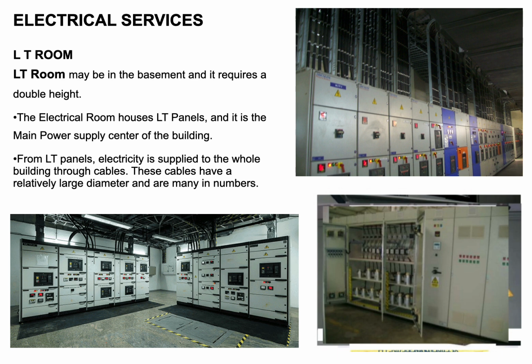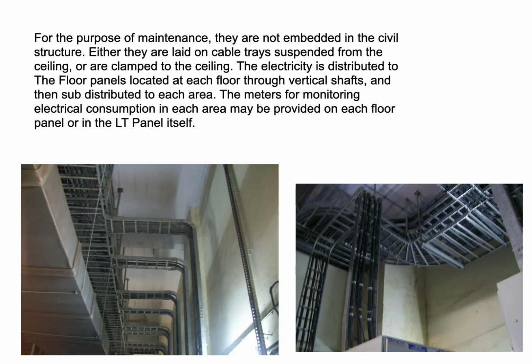The electricity is distributed to the floor panels located at each floor through vertical shafts and then sub-distributed to each area. The meters for monitoring electrical consumption in each area may be provided on each floor panel or in the LT panel itself. All critical areas have their own individual floor panel for electrical and their individual uninterrupted power supply or UPS, which is connected to a centralized UPS. Power backup for all essential services has to be provided.